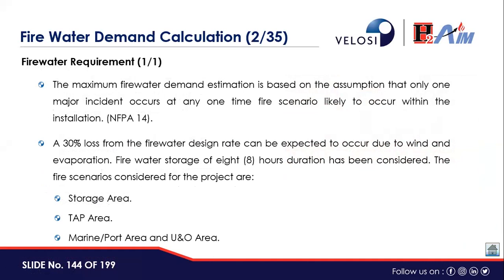So these are the firewater requirements. The maximum firewater demand estimation is based on the assumption that only one major incident occurs at any one time, the fire scenario likely to occur within the installation as per NFPA 14. This is the requirement of NFPA 14, the assumption. A 30% loss from the firewater design rate can be expected to occur due to wind and evaporation. Firewater storage of 8 hours duration has been considered.